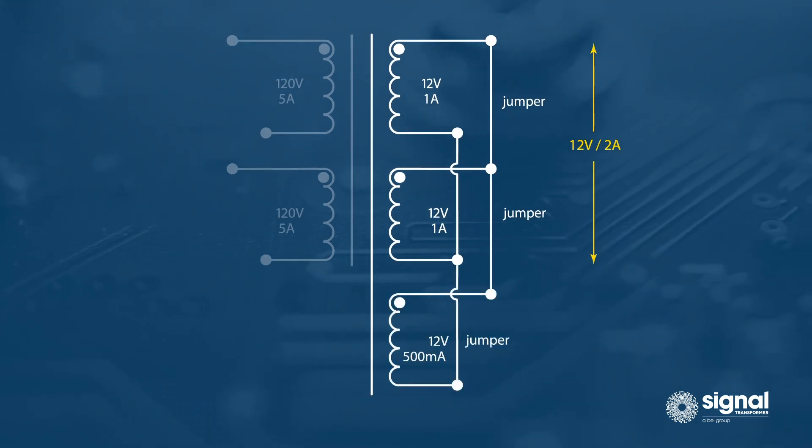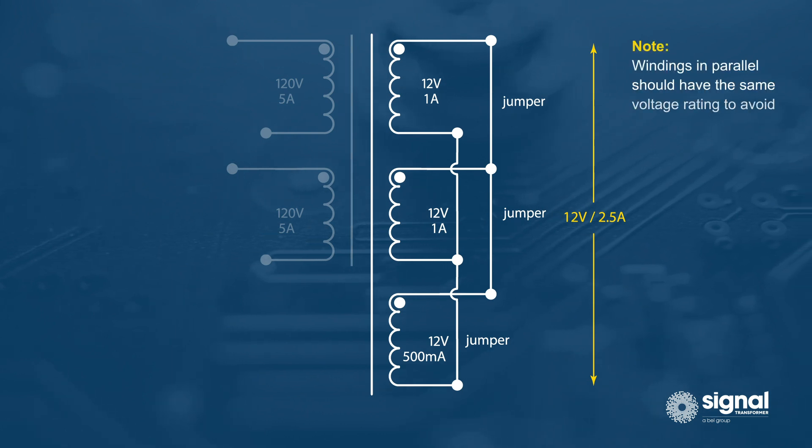Adding a 12-volt 500 milliamp winding in parallel increases the output rating to 2.5 amps. Note that windings in parallel should have the same voltage rating, as dissimilar ratings can result in a hazardous condition.